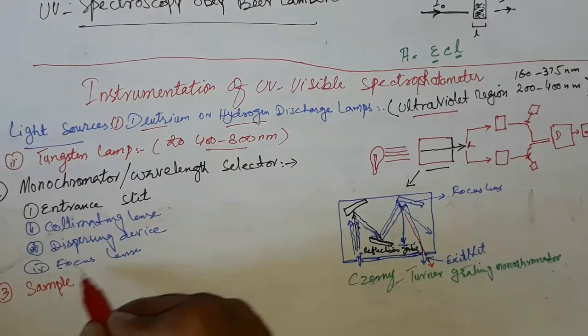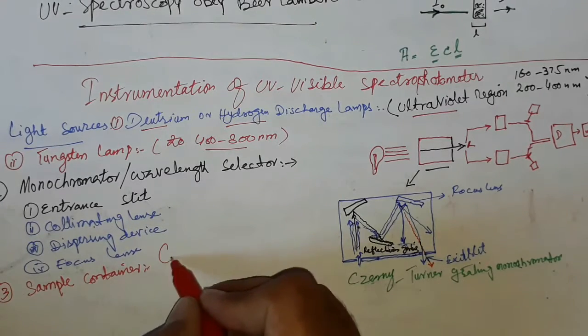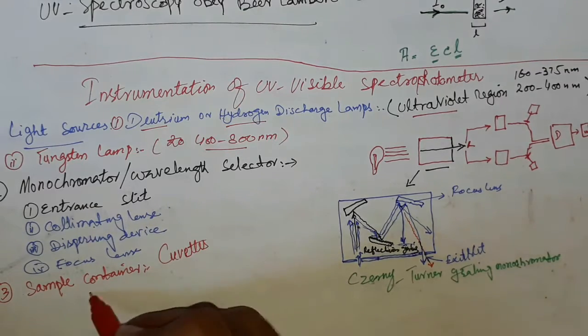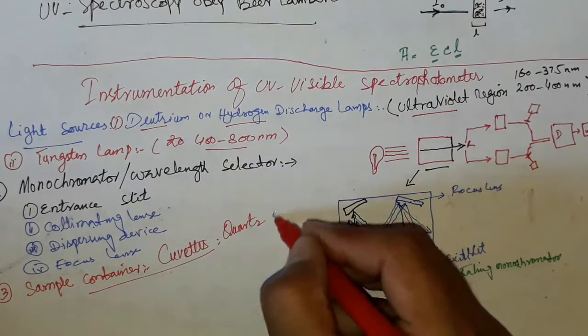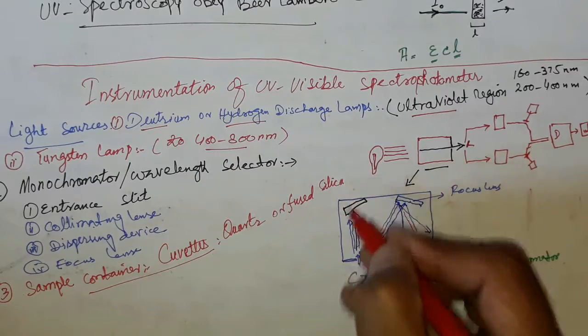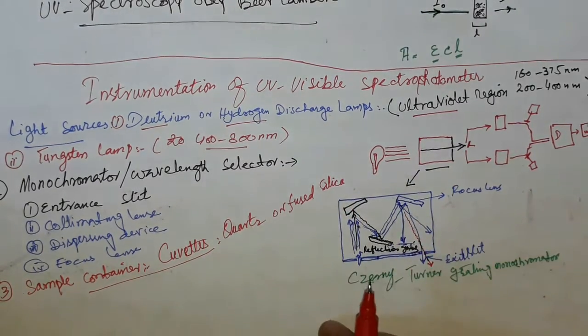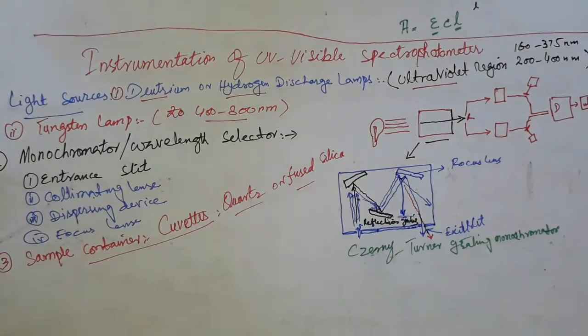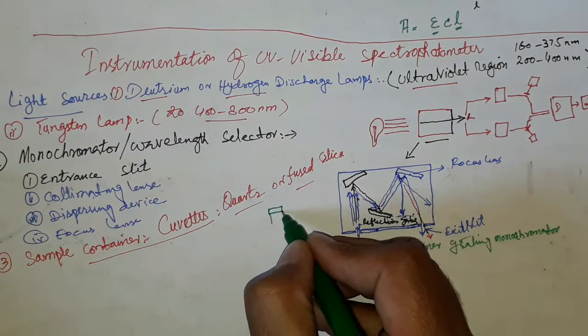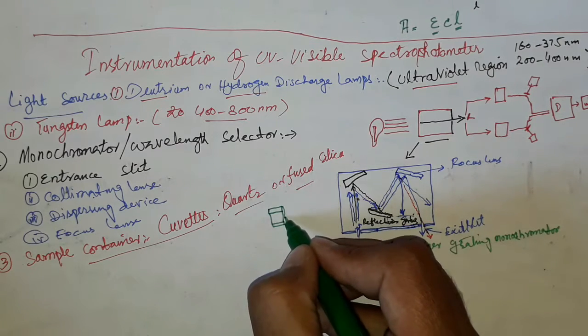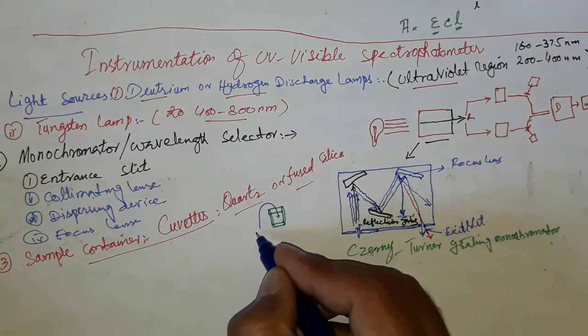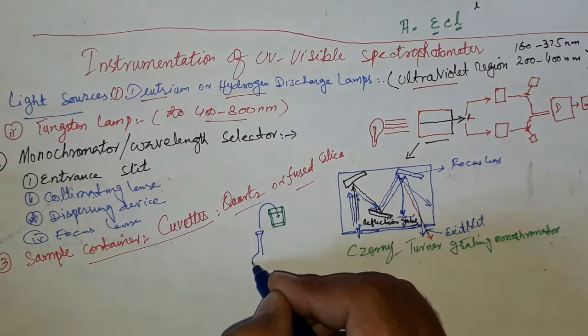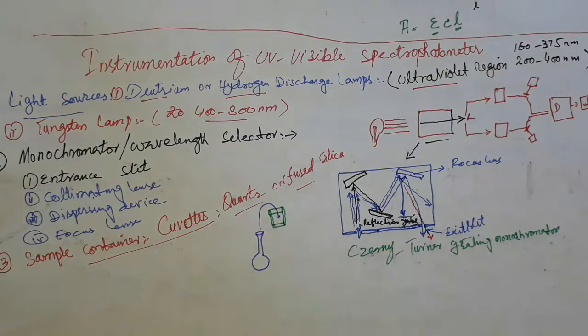The next important component is the sample container. Sample containers are also called cuvettes. They are made of quartz or fused silica, not of glass, because glass may absorb radiation in the ultraviolet-visible region. They are extremely costly, so during handling these cuvettes must be used with caution. The sample solution is transferred into the cuvettes for analysis and then they are placed in the cuvette holders.